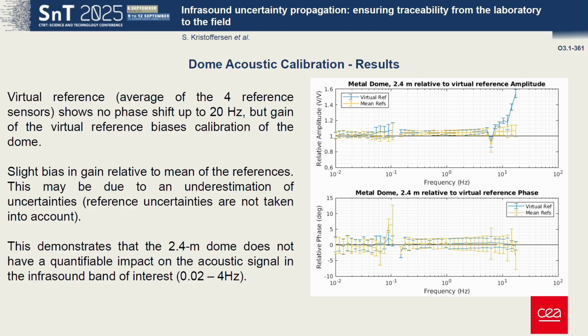And we can see here the blue is showing the results relative to the virtual reference, and that gain goes up, but that's in the blue, and it stays flat in the yellow, which is the comparison with the average of each individual reference calibration. But that blue curve going up is because there's basically a transfer function associated with that virtual sensor. So it's not actually the sensor under test or the dome. And we can see that when we do the mean references, we get a flat response.